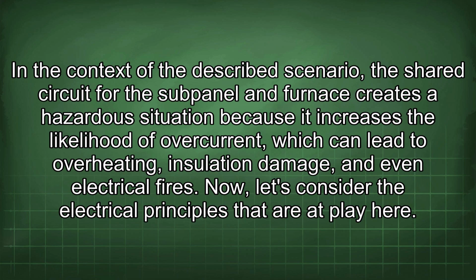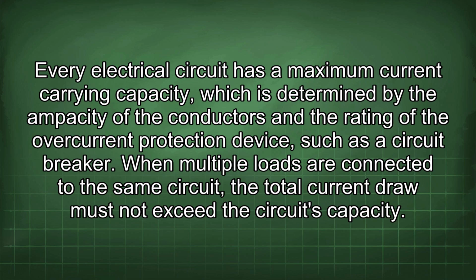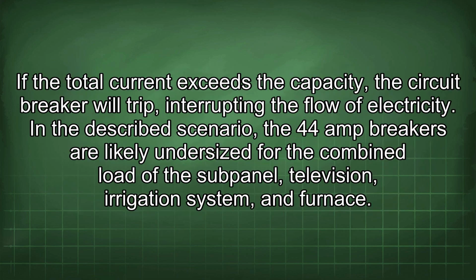Now let's consider the electrical principles that are at play here. Every electrical circuit has a maximum current carrying capacity, which is determined by the ampacity of the conductors and the rating of the overcurrent protection device, such as the circuit breaker. When multiple loads are connected to the same circuit, the total current draw must not exceed the circuit's capacity. If the total current exceeds the capacity, a circuit breaker will trip, interrupting the flow of electricity.